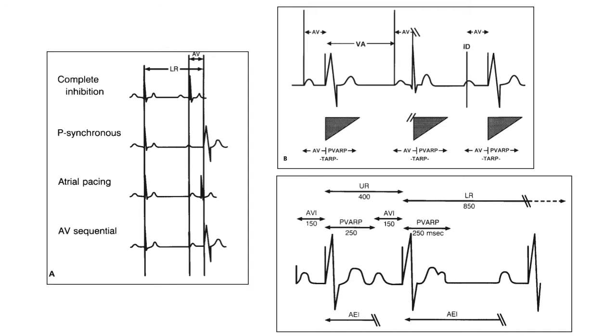This period prevents the sensing of inappropriate signals, such as T waves, from inhibiting pacemaker firing. And we have seen in single chamber systems capable of sensing, each sensed or paced event will be followed by a refractory period. Once this refractory period ends, the amplifier will become alert and able to detect native signals again. The pacemaker acts like the heart and has a refractory period that consists of two parts. The first part is the absolute refractory period, during which any native activity cannot be detected, and this is called the blanking period. The terminal part of the refractory period is relative and events can be sensed, but these events are not used to trigger or reset the output of the pacemaker.